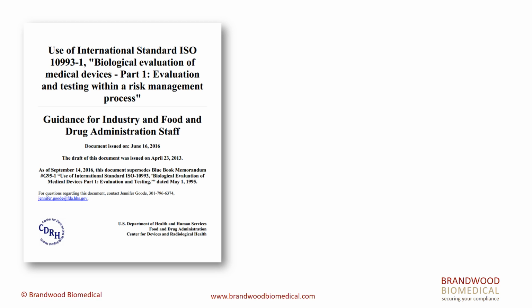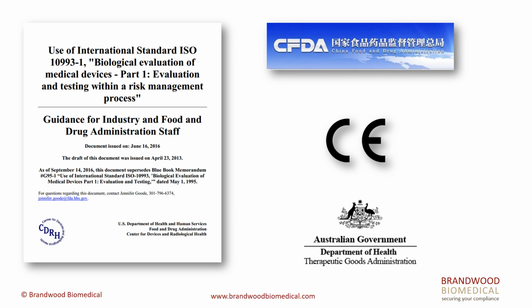But the FDA in the US is not the only agency. Other agencies around the world do this as well. China particularly, I was recently lucky to be part of a delegation which did a special symposium with the China FDA, working specifically with the reviewers on how to use the risk management model, and the China FDA certainly accepts risk-based submissions and does not require complete testing, which is a complete change from the practices of a few years ago. And the same is true in Europe, and here in Australia our own Therapeutic Goods Administration very much is prepared to accept risk-based submissions dealing with biological evaluation.